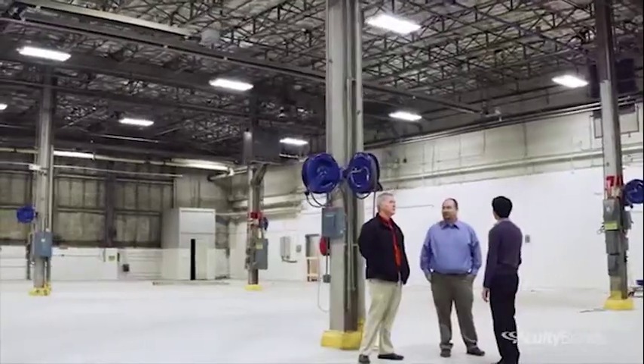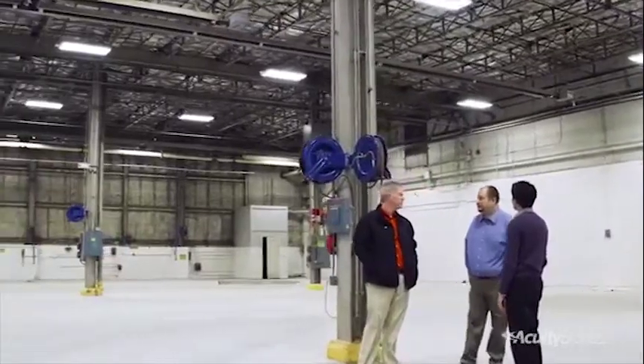Alarms went off right there — typically for a warehouse you want 30 foot candles and they wanted more than double that. I had already ran some preliminary calculations and already knew that the space could be relit as a one-for-one. From that point I just talked to the owner about what we would be giving them, which would be a design space and a control scheme that could be used for this tenant and future tenants.